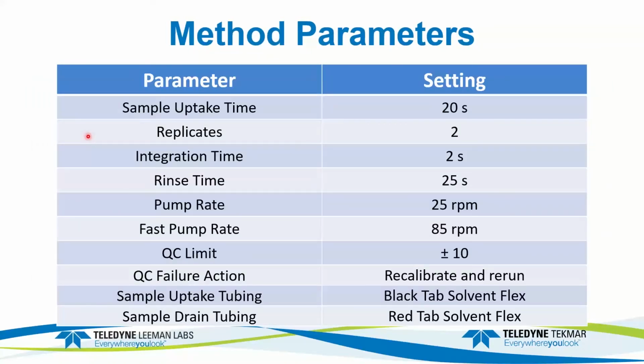Other method parameters that we use: because we're increasing the speed, we can take the sample uptake time from what was 50 seconds in the original application and reduce that to 20 seconds by increasing the speed of the pump during uptake. If we increased it more, then that sample uptake time can be shortened even more. We're going to do 2 replicates of 2-second integrations. Rinse time was set to 25 seconds, and that is concurrent with some of the analysis time, so we're saving a little bit of time there. The normal pump rate when we're making analytical measurements is 25 RPM.